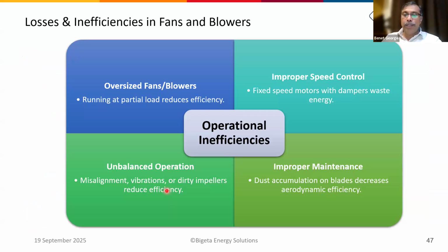Then second, improper speed control. In many cases, to reduce the flow, people use a damper. Whenever you have a damper, you are losing energy across the damper. So we can have a variable frequency drive and reduce the speed based on the requirement, which will reduce the energy consumption. Then misalignment, vibrations, and impeller problems, which can cause unbalance, also reduce the efficiency. Then improper maintenance, especially in fans and blowers, such as dust accumulation, also affects the efficiency of the system.